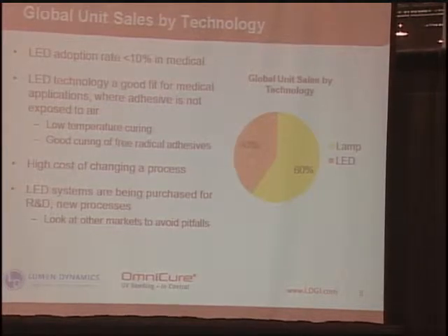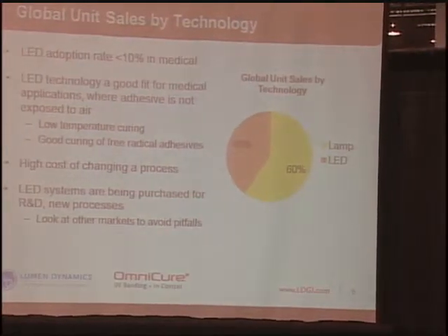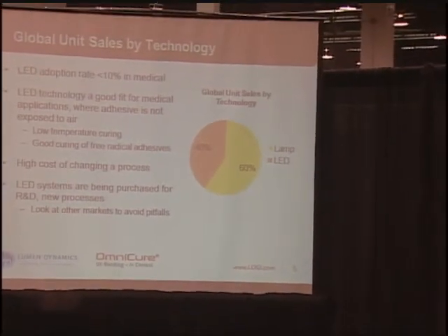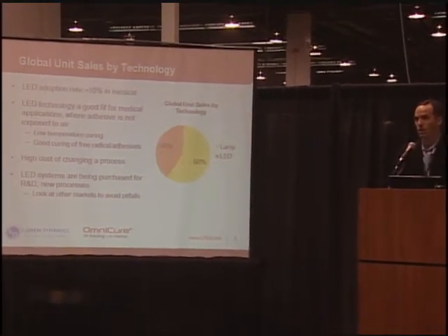Certainly one of the things we're aware of is there's a very high cost in changing anything within a medical device assembly process. So there's a difficult justification to make to switch from a lamp to an LED, and we understand that's part of the reason limiting adoption. The other being the lack of an accurate radiometer, which again is something we think is being addressed recently with some new product lines. So really what we're seeing at this point is LED systems in medical, at least, really being purchased for R&D requirements, for testing, or for new processes.